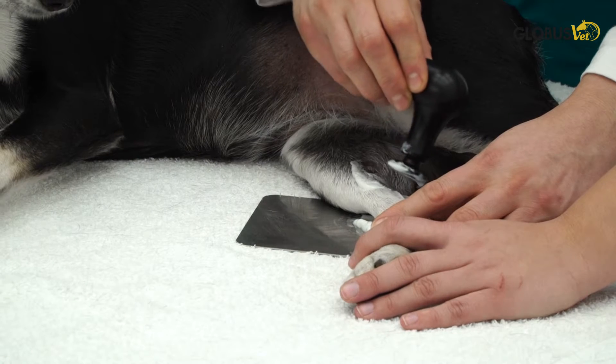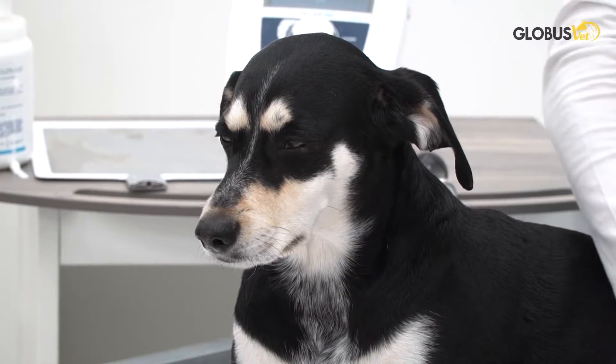The capacitive modality is applied using an isolated electrode. This modality acts mostly on the soft tissues in close contact with the electrode that are rich in water content, like skin, connective tissue, blood and lymphatic system, and muscle. It is especially useful for treatment that needs to be delivered superficially. The resistive mode is delivered by a non-isolated electrode, helping the operator reach tissues with a lower percentage of water and a greater resistance to the passage of electric charges — an excellent technique for bony changes, cartilage lesions, and tendinous and ligamentous conditions.